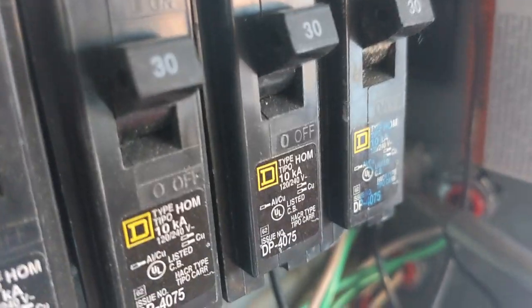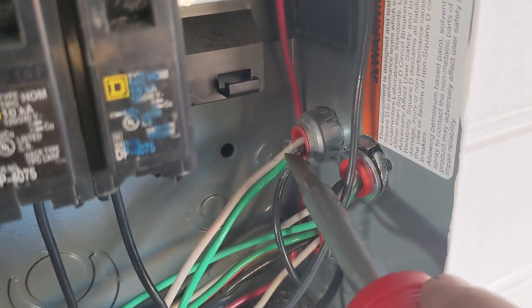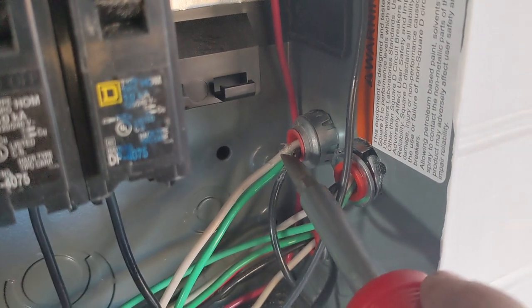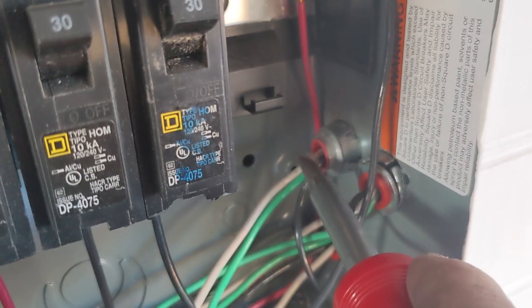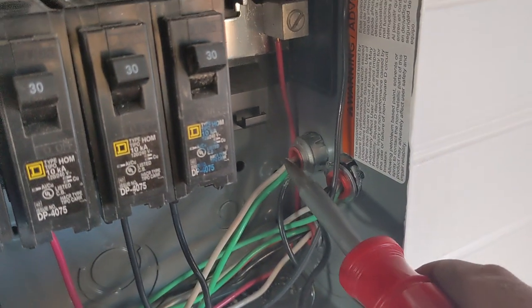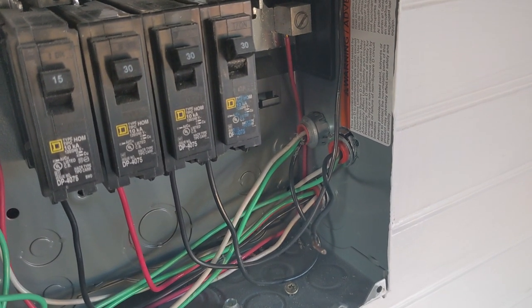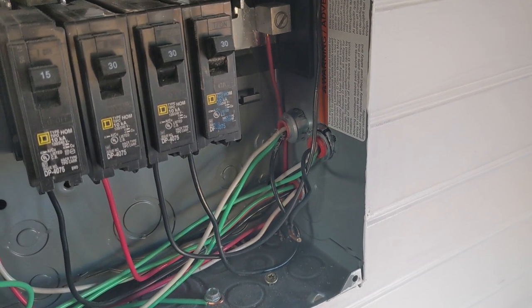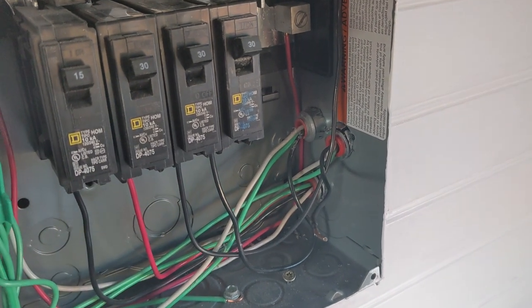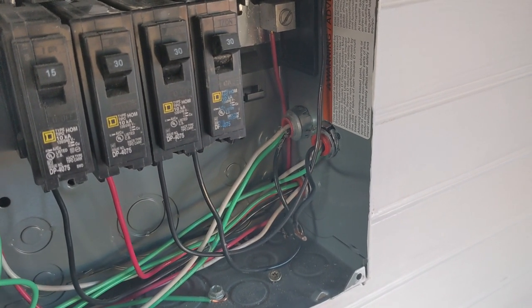If you remember from before, that insulation back there is torn, and you can see copper on the black, which will be the line, and then there's copper exposed on the neutral. I'm guessing what they did is they tried to cut the MC — that metal armored cable, the flex — with a hacksaw or something instead of using a proper cutting tool. So I am going to show you a quick cut on some MX cable and what it should look like.